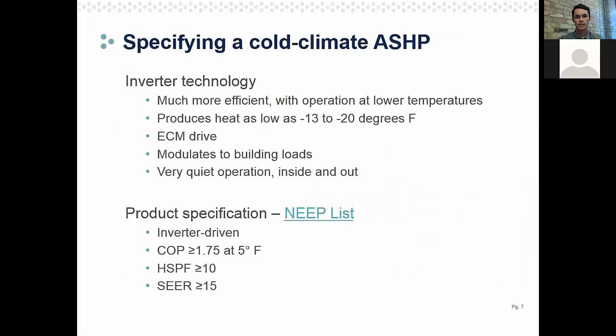So what makes a heat pump cold climate? Really what changed in 2013 was this inverter technology. So they're much more efficient devices or condensers, so they're able to extract heat at these low temperatures, and they're able to deliver that heat into the home at efficient levels. They're able to move heat at -13 and all the way down to -20 degrees. We found in our studies they're actually able to move that heat at those low temperatures.